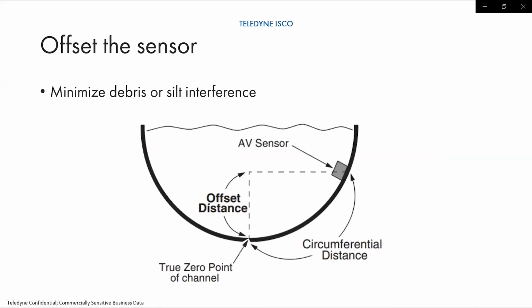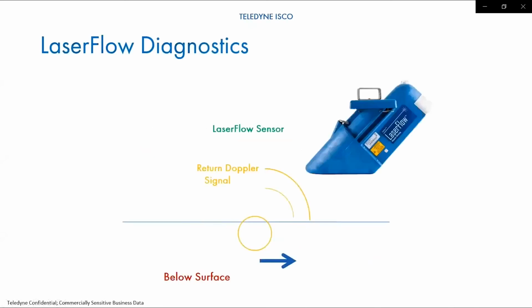Now, if you do have problems with debris where you have to go out there quite often to clean that application, one thing you can do is just offset the sensor, rotate it up to the side. That way all your debris and everything just falls to the bottom and washes right past the sensor. Now, keep in mind, normally you're calibrating your sensor to zero right here at the bottom, but if you rotate it, then you would calibrate it to the actual water depth. So if this is 6 inches, I calibrate the level to 6 inches here at the bottom. If I rotate it to the side, I still calibrate my level to 6 inches, and it should continue to track properly with the change in level.